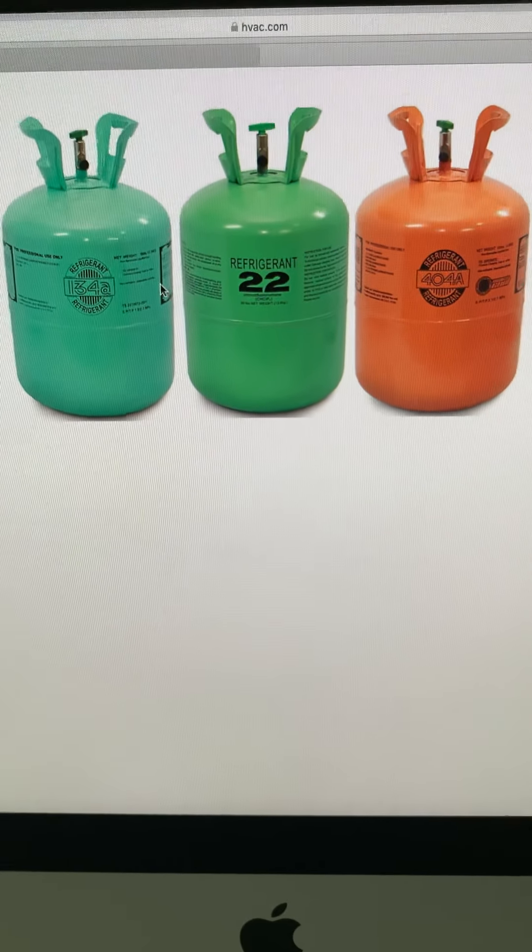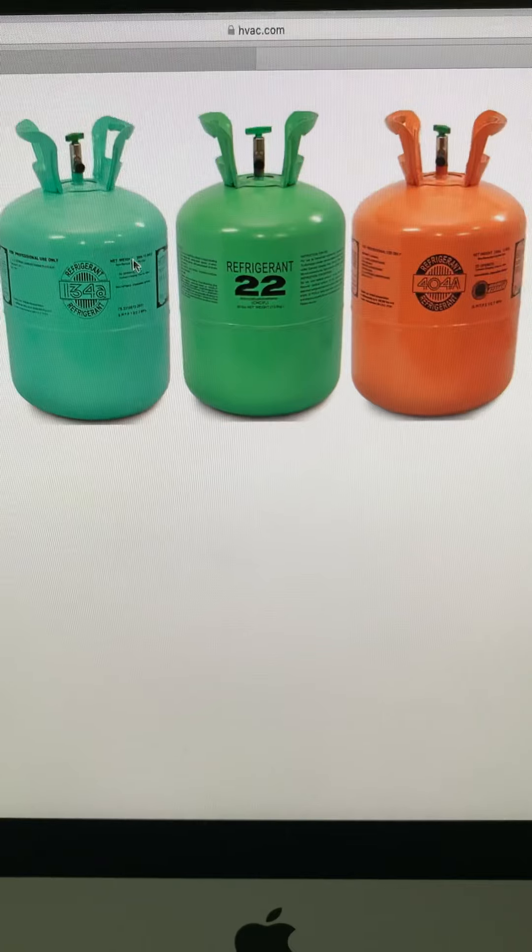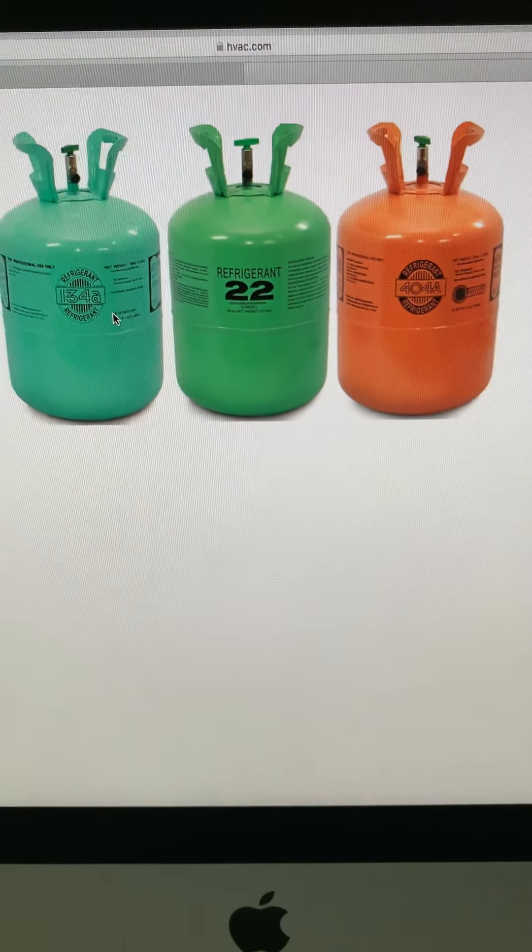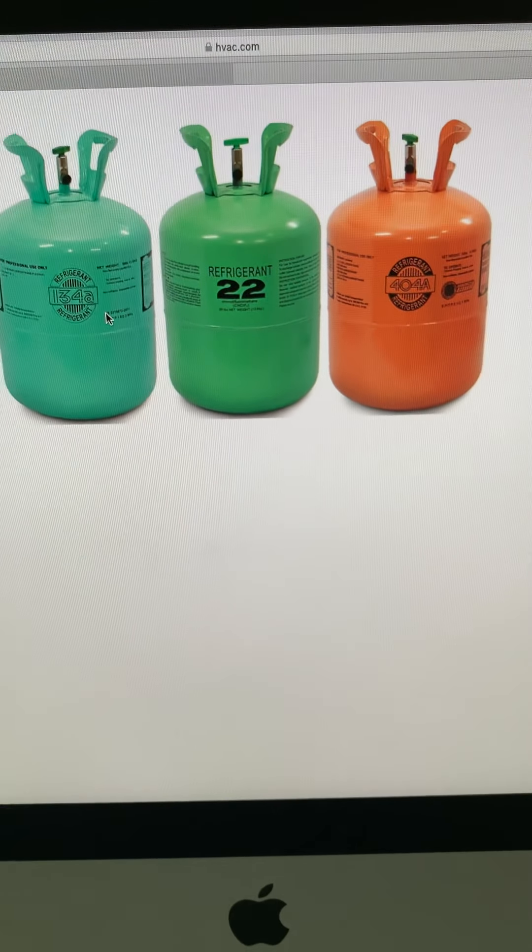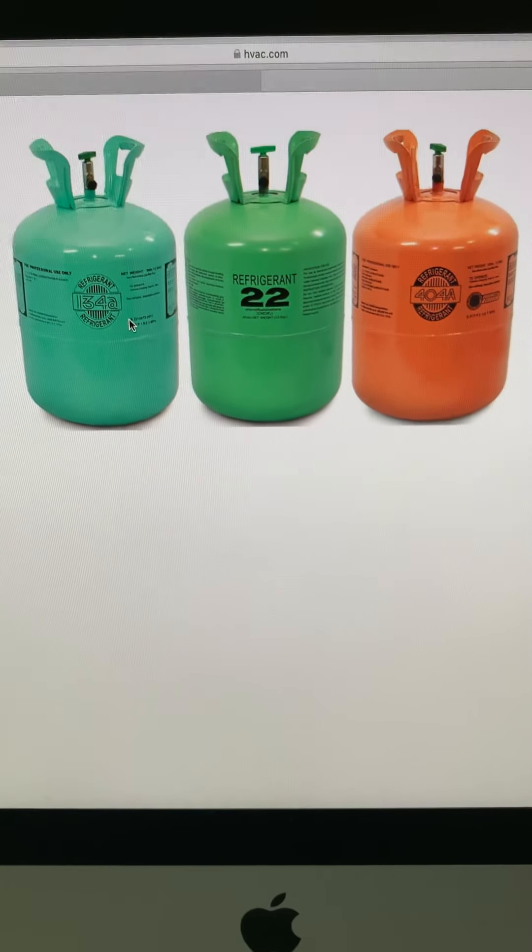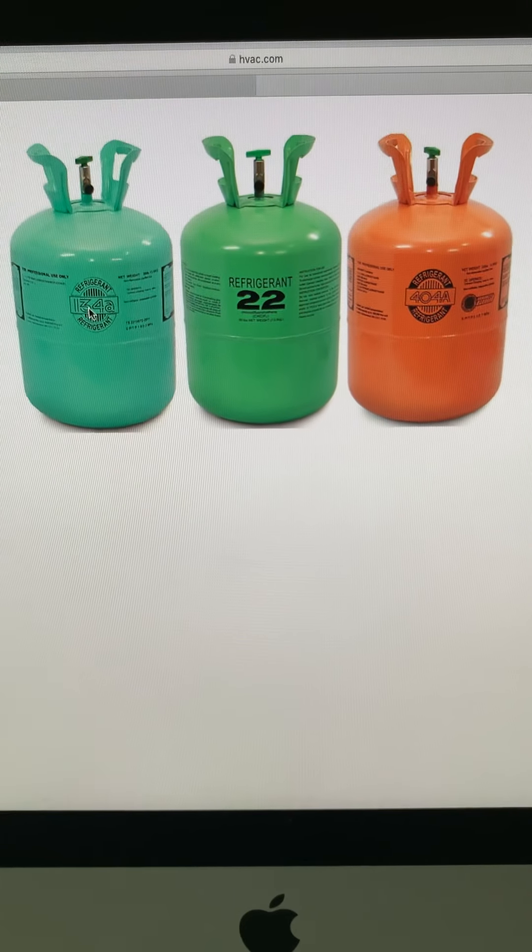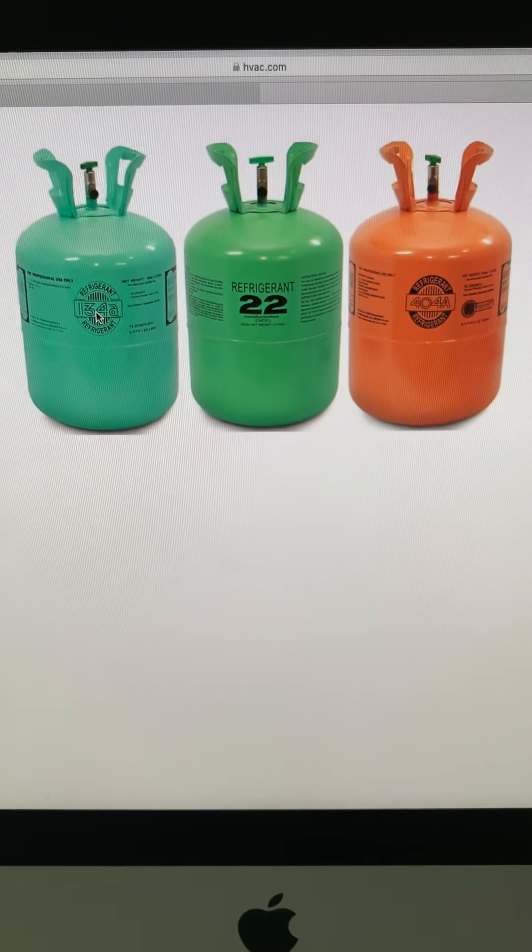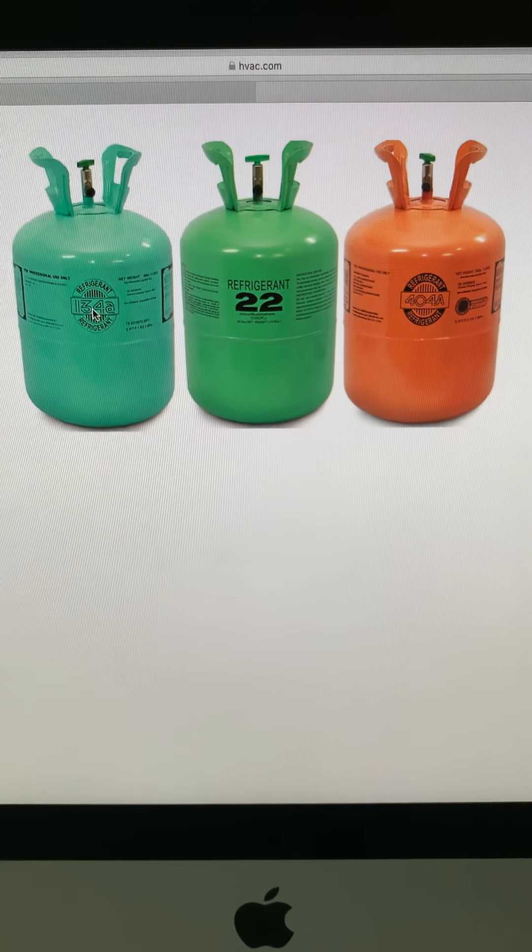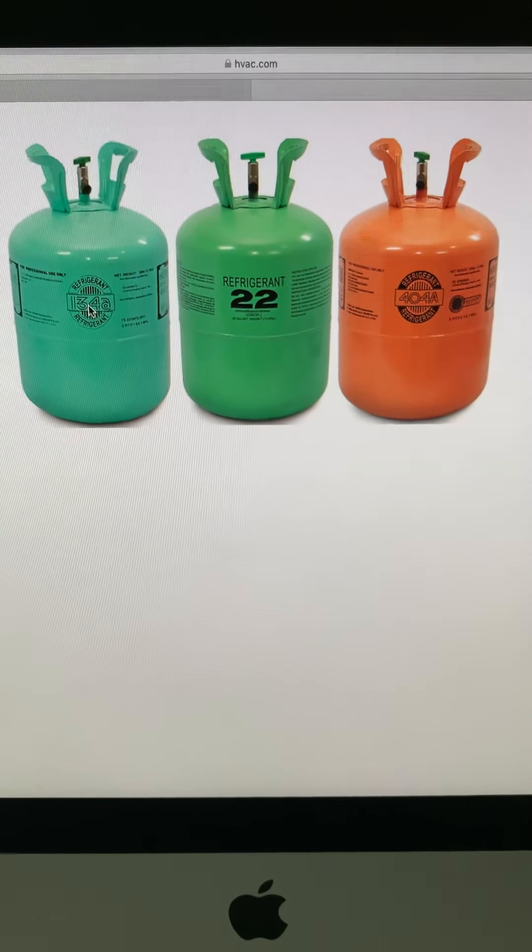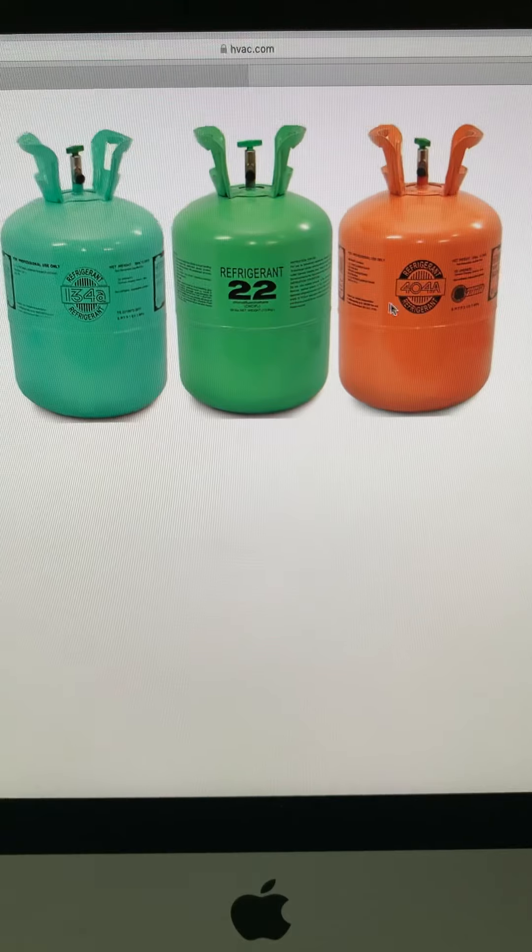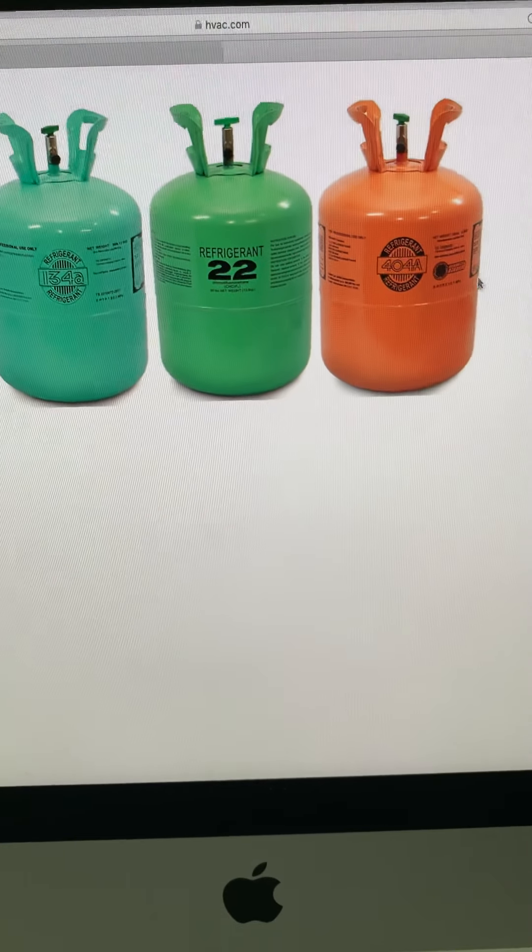The simple explanation is 134A is used for fresh applications. Fresh is anything that is 40 degrees Fahrenheit, 32 degrees Fahrenheit, something that needs to be transported fresh. 404A is for frozen applications.